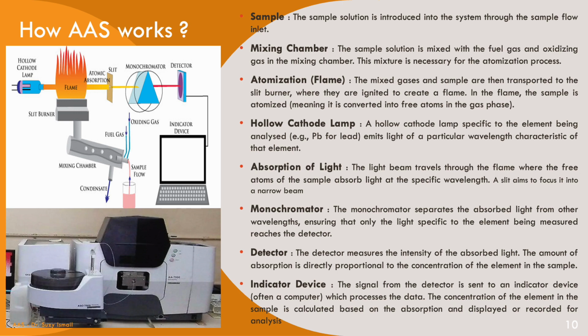So the sample solution in the mixing chamber will mix together with fuel gas and also oxidizing gas, right? This mixture is necessary for the atomization. Remember, atomization means that you are producing atoms from your sample solution. Atomization is in the flame part. The mixed gases and sample are then transported to the slit burner.